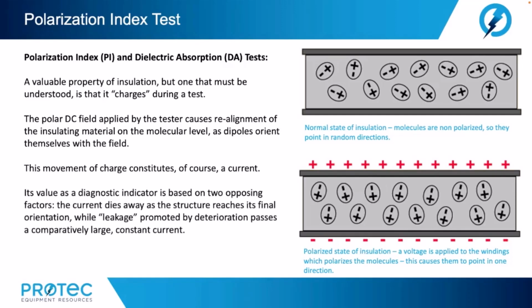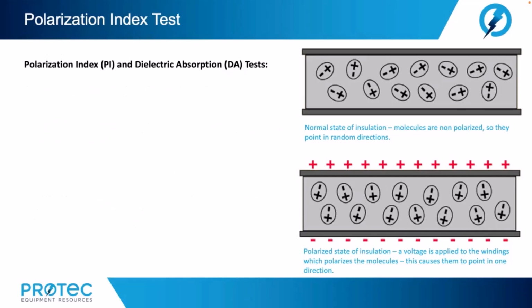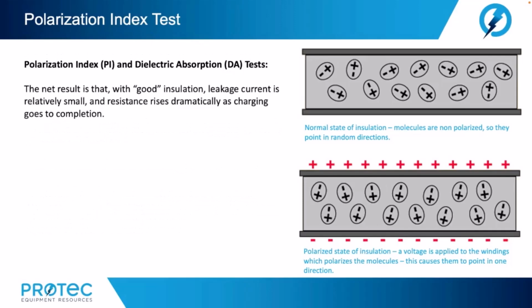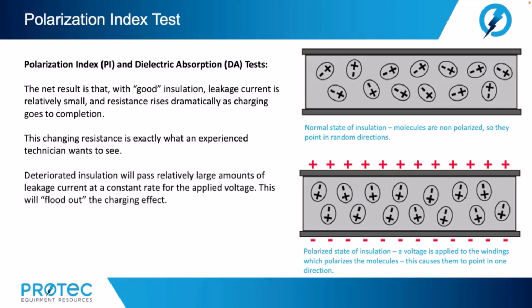This movement of charge constitutes, of course, a current. Its value as a diagnostic indicator is based on two opposing factors. The current dies away as the structure reaches its final orientation, while leakage, promoted by deterioration, passes a comparatively large constant current. Now, the net result is that with good insulation, leakage current is relatively small and resistance rises dramatically as charging goes to completion. This changing resistance is exactly what an experienced technician wants to see. Deteriorated insulation will pass relatively large amounts of leakage current at a constant rate for the applied voltage. This will flood out the charging effect.